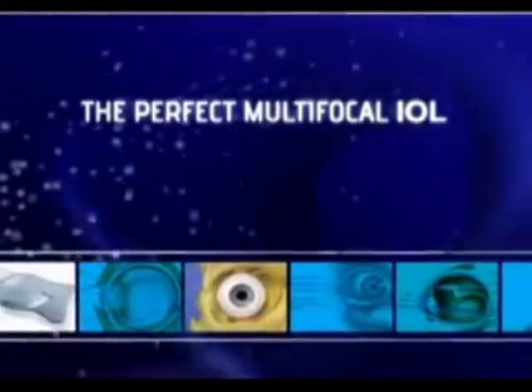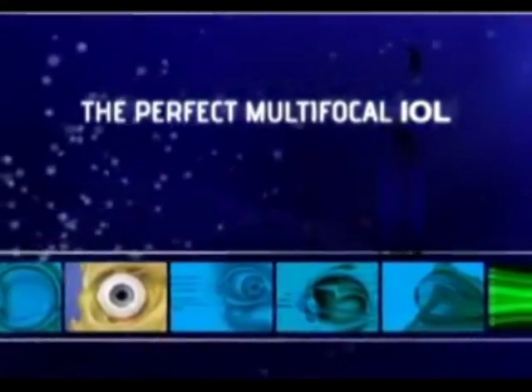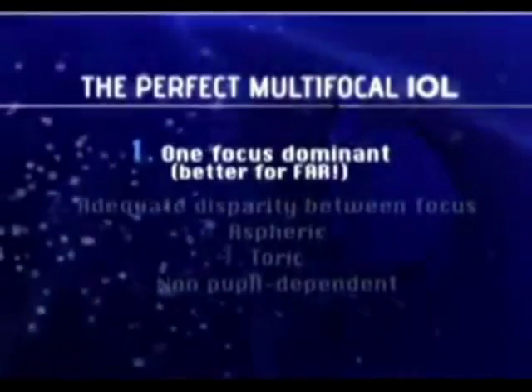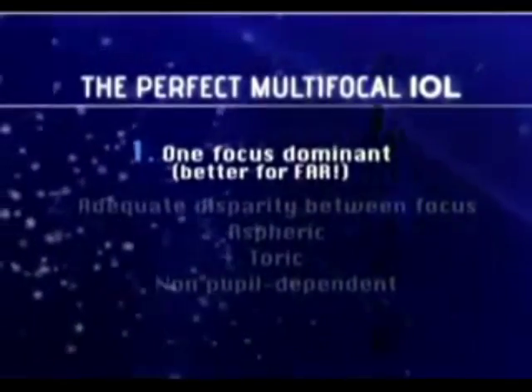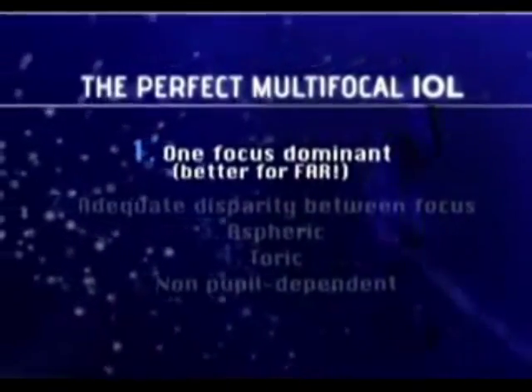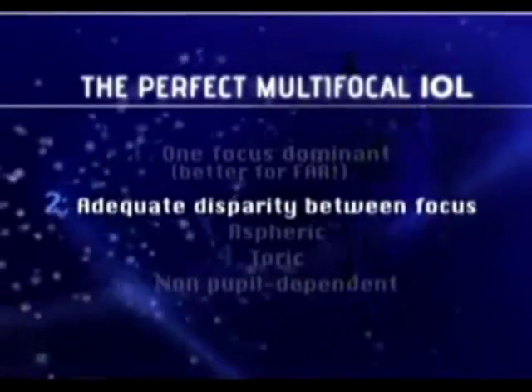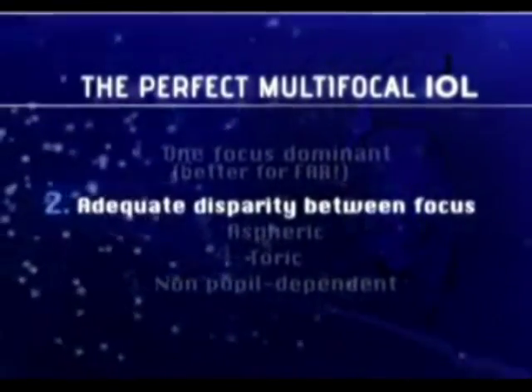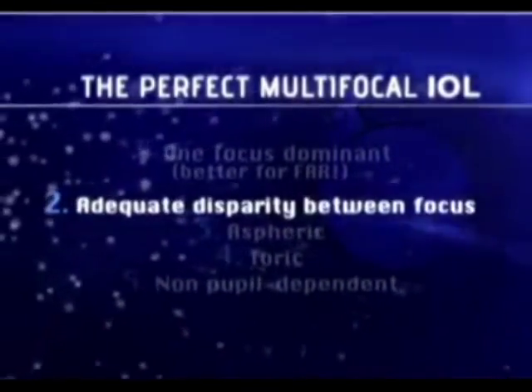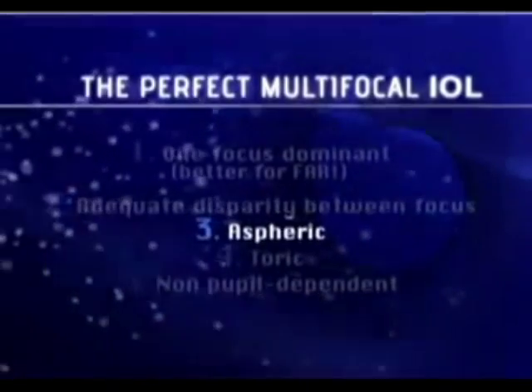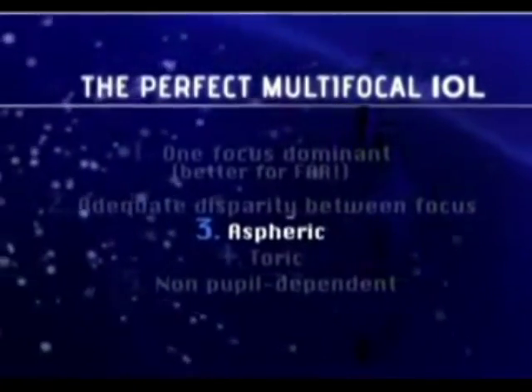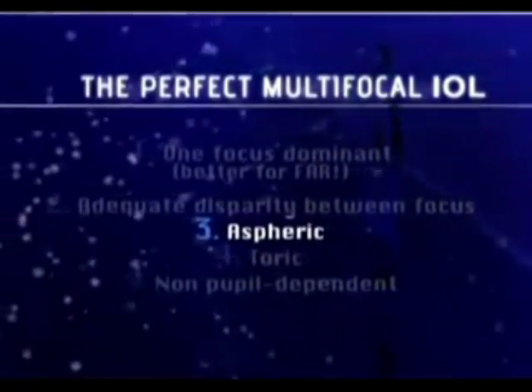The first things that we would like to define are the characteristics of the perfect multifocal intraocular lens. The perfect multifocal lens should have a focus which is dominant for far. It should avoid the overlapping of foci, providing the adequate disparity between foci. It should be aspheric in order to improve the optical performance.